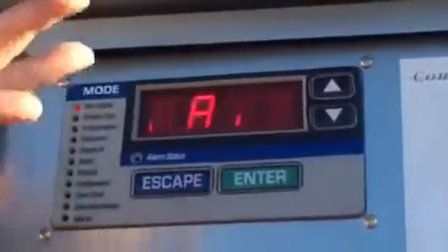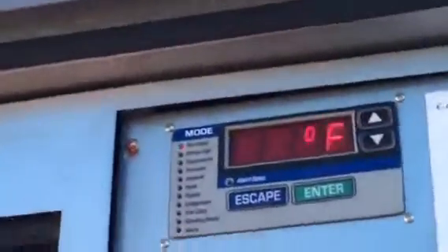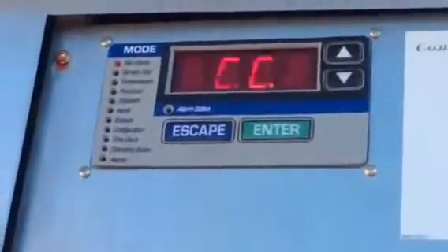And we just showed that blinking light, the force was clear. But on the actuator, like economizer, we can go in and calibrate it with this through the marquee, force it to run 0 to 100% so it learns its position, and it may come back that the calibration failed. It can't, which would be an indication I may have a problem with the actuator. And manually, I can always go in and force it to a certain position also.